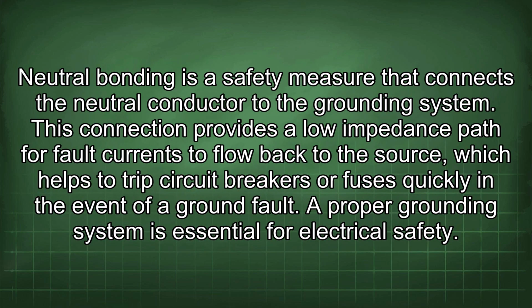Neutral bonding is a safety measure that connects the neutral conductor to the grounding system. This connection provides a low impedance path for fault currents to flow back to the source, which helps to trip circuit breakers or fuses quickly in the event of a ground fault. A proper grounding system is essential for electrical safety.